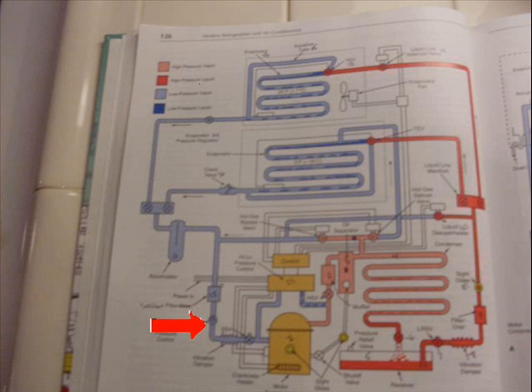Okay, now the last valve that's on there, it's going to be a little hard for me to explain to you guys. Some people leave it out. I'll do my best explanation. You're welcome to read the book. I'm used to calling it a CPR, compressor pressure regulator. What does the book call it? Low side pressure control. The job of that valve is to maintain a constant pressure to the compressor.